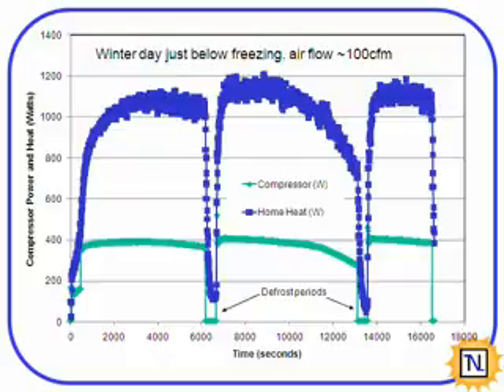Another important consideration with our system, since it is an air source heat pump, is defrosting. It's much like your refrigerator, in that the evaporator moisture is going to condense and freeze on it, and at some point, as it restricts airflow and heat transfer, you need to get rid of that frost. So these are two defrost periods that we instigated in the system, expelling that frost from the system.